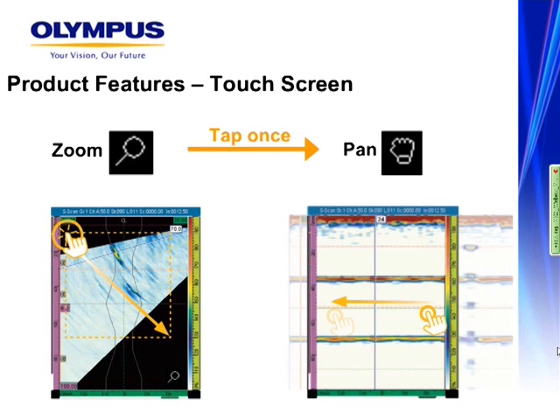The touchscreen has 3 modes of operation: zoom, cursor manipulation, and gate manipulation. The mode is displayed with an icon in the upper right-hand corner for one of the 3 modes. Zoom is displayed here. While in zoom mode, the operator can zoom as desired directly on the display by creating a box with one finger on the active data window. Use of the zoom function key also allows the operator to unzoom and zoom on gate position, on cursor parameters, zoom to center, zoom to corner, etc. By default, the MX2 is always in zoom mode until either the cursor or gate mode is selected.